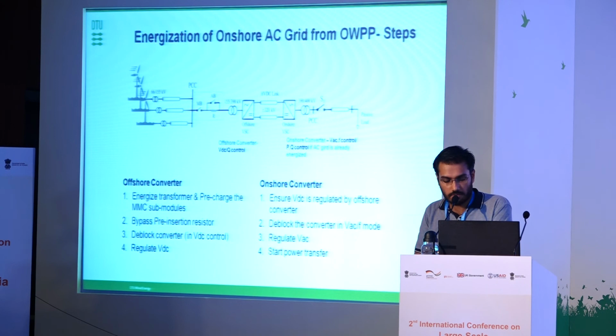This is the system that I'll be showing the initial study results about. It has a wind plant with some sort of aggregation, and then the offshore transformer with a PIR to deal with inrush transients, detailed MMC models, an HVDC cable link of about 400 kilometers, and then the passive load. But this is just an example system. Of course, a more realistic scenario can be used. However, this was just to see if it is possible to Blackstart the onshore side by wind turbines.